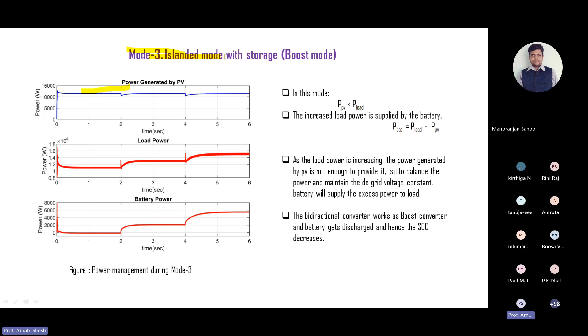Here you can see it is 11 kilowatt generation constant. Now your load power is almost 11 kilowatt. So generation is 11 kilowatt, load power is also 11 kilowatt. So as per the power management algorithm, the battery power is 0 kilowatt first.